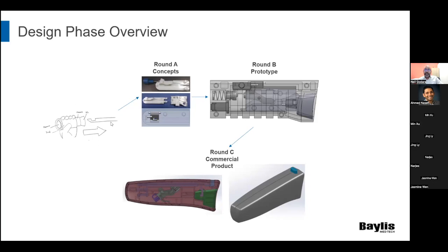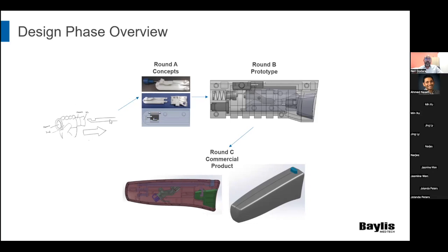We had a device, which is a suture passing instrument. For a particular market reason, we had to ship it without suture preloaded. So we needed a way that the end user could load this instrument. It's a fairly complex instrument. It doesn't look like it here, and it has complex knots and all sorts of stuff. And we said, okay, we can't have the user tie these complex knots.